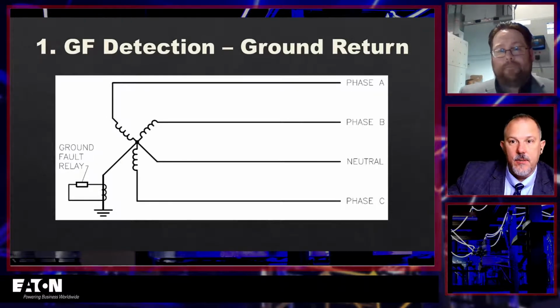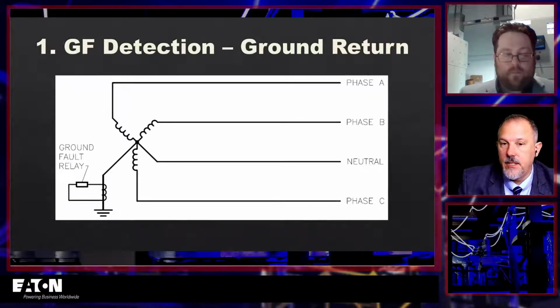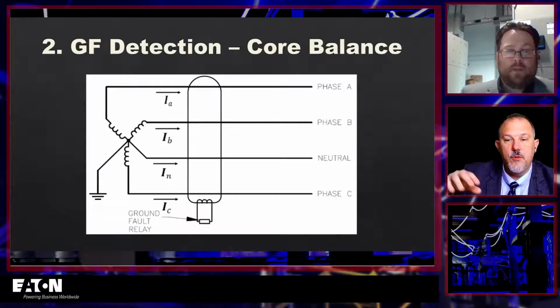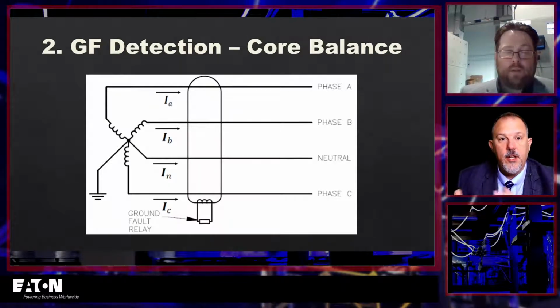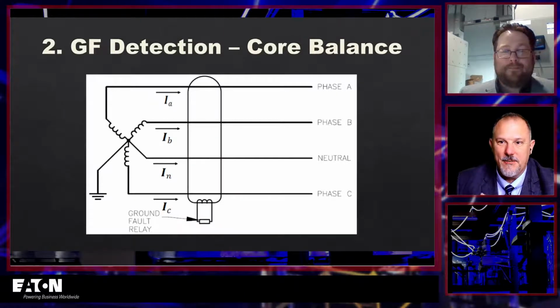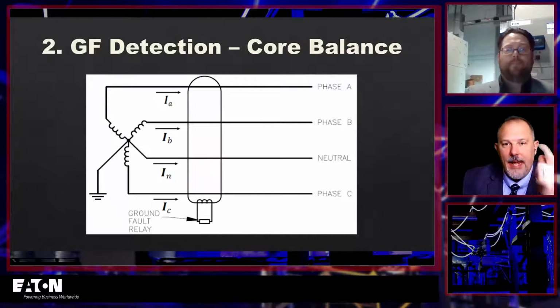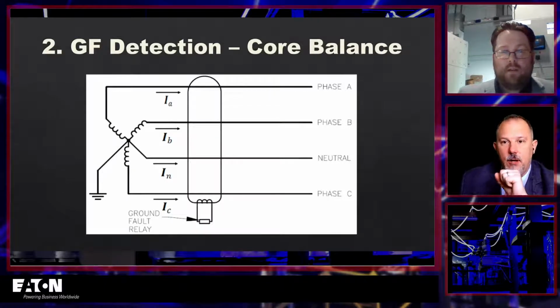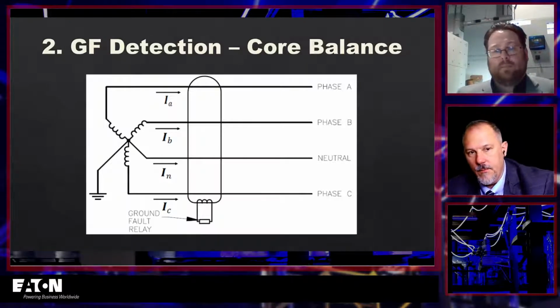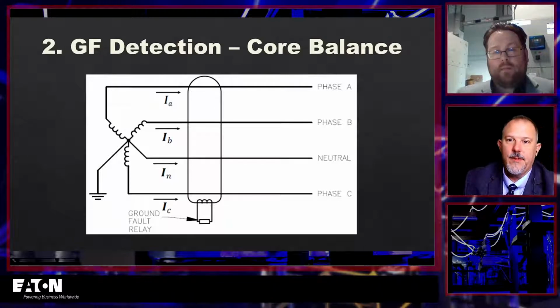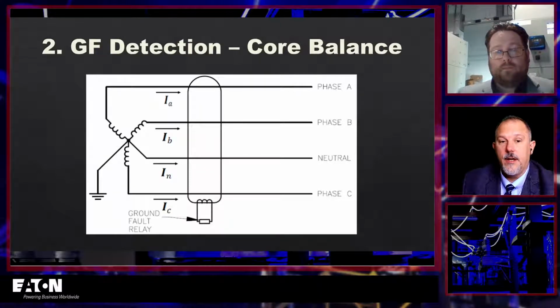So this is one method, where you have a ground fault relay in that ground. Another method would be to use a zero sequence CT. We know that A, B, C, and neutral would go through that donut, but not your equipment grounding conductor. A, B, C, and neutral should all add to 0. If I see currents greater than 0, allowing for errors and margins, or greater than a threshold, then I know I've got a ground fault out there, and I open up.